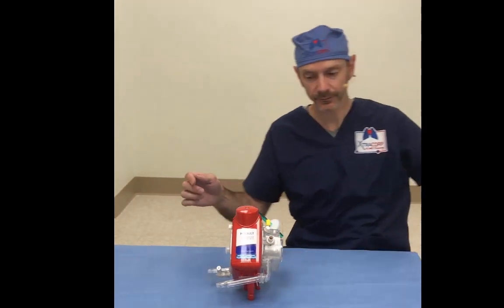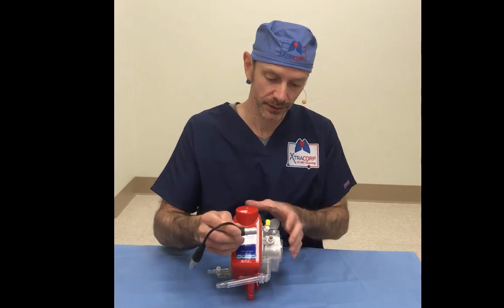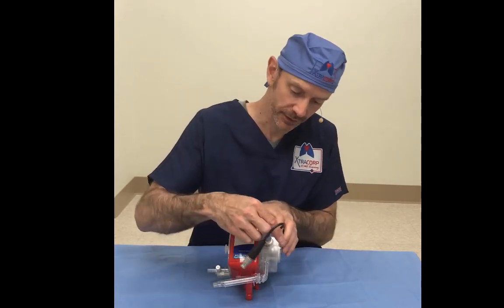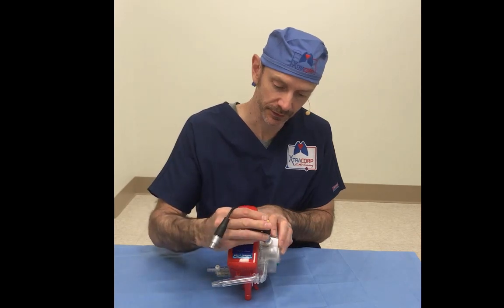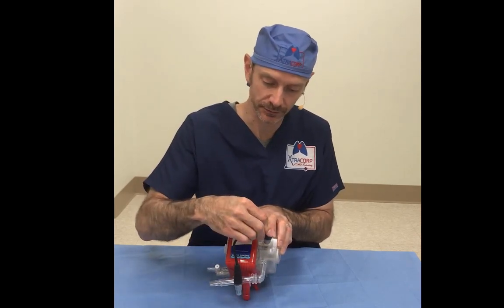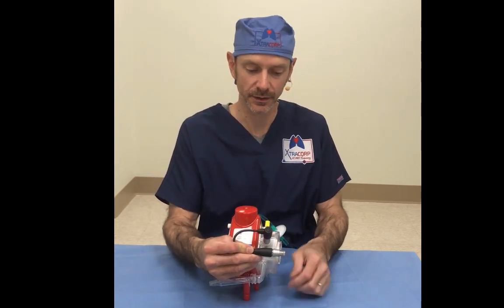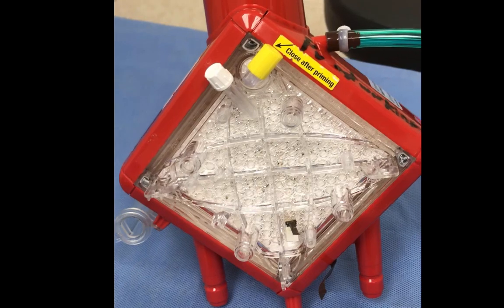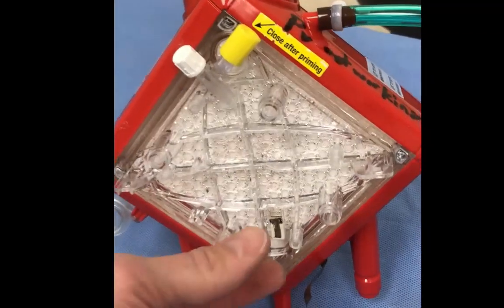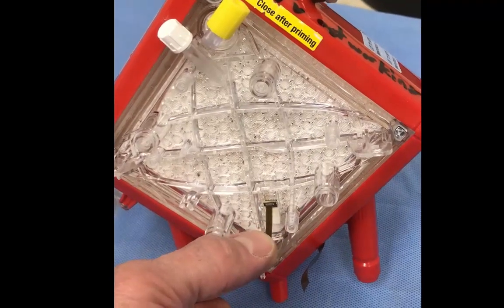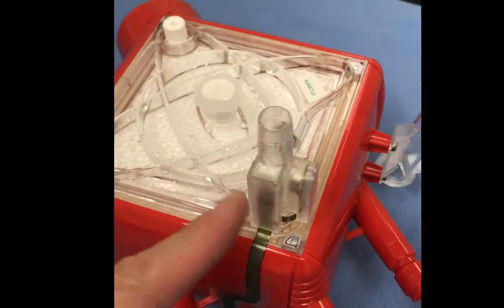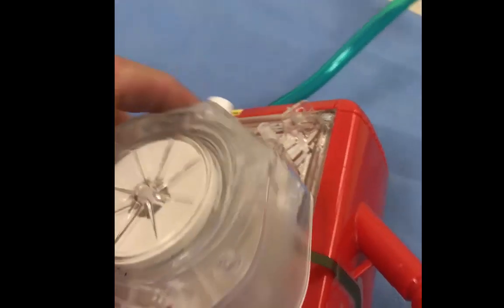By connecting our data cable, and that data cable has a red dot here and a red dot there, and if it's on like this, turns back across the oxygenator. And then that would fit into the Cardiohelp console. Pre-membrane pressure sensor. Post-membrane pressure sensor. Electric cable runs around the side, goes into the space here, the Never Never Land that nobody gets to see unless you happen to have one of these that you can tear apart.